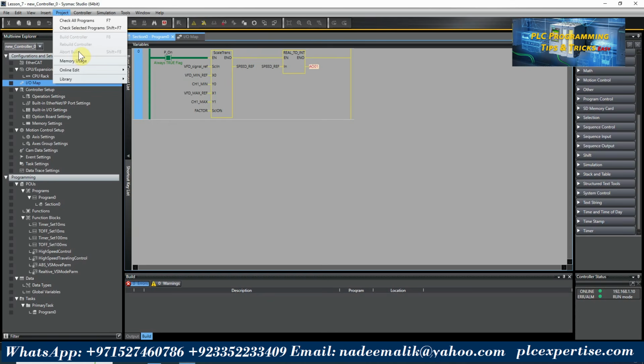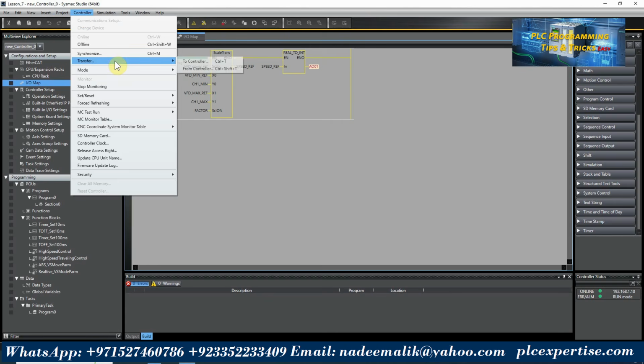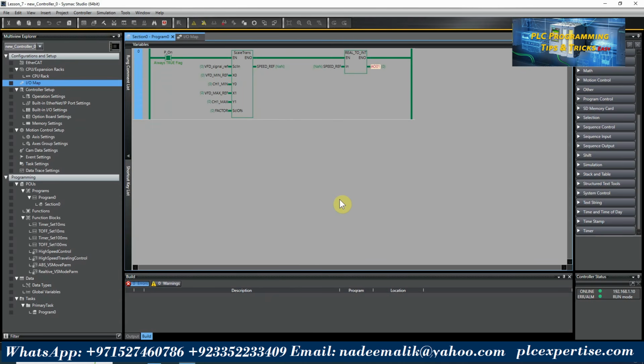Go to the project controller, transfer to controller. Now we have to modify all of these parameters. Now we have to enter some minimum and maximum values for these inputs. First of all is a minimum speed reference. We will put here 0. Maximum speed reference is 50. Minimum channel value is 0 and maximum will be 4000.